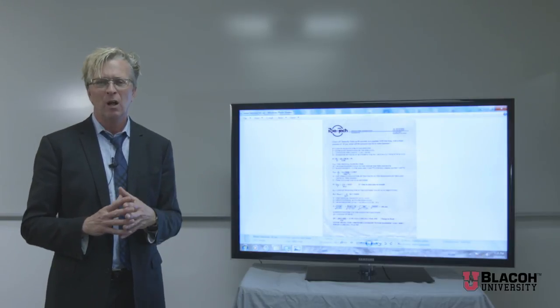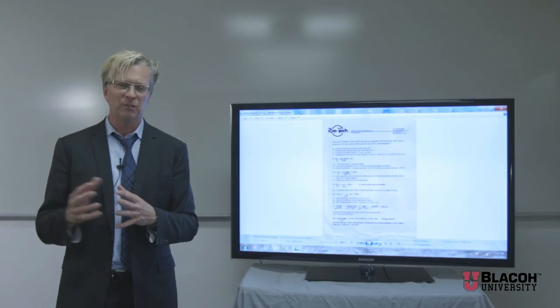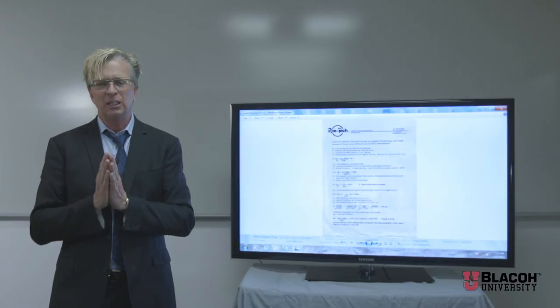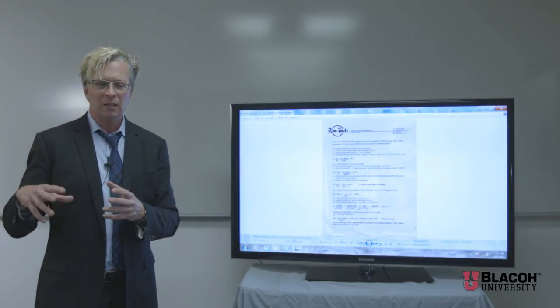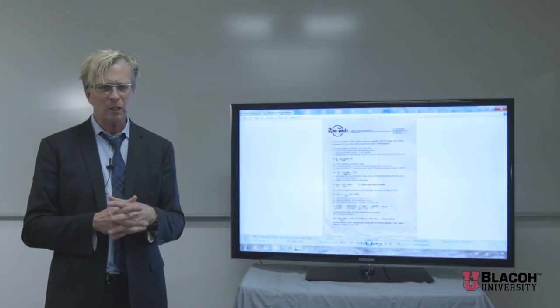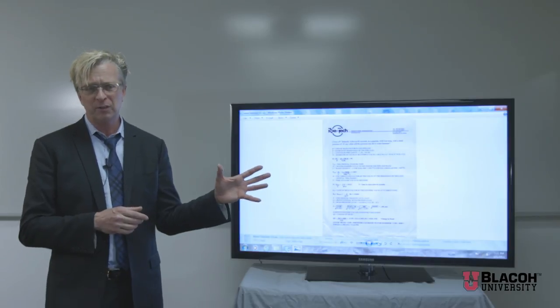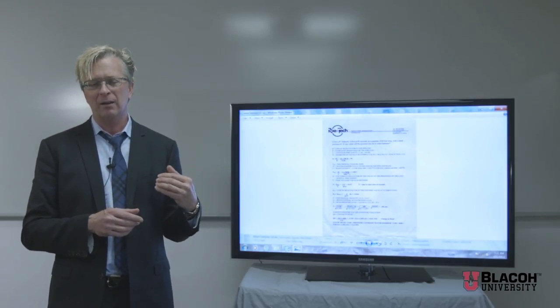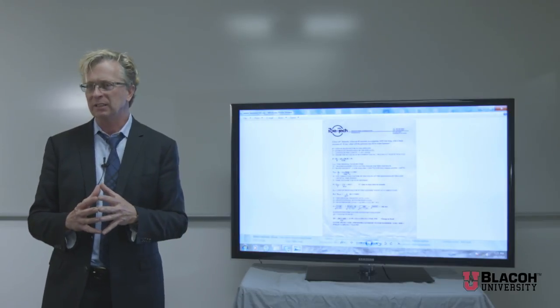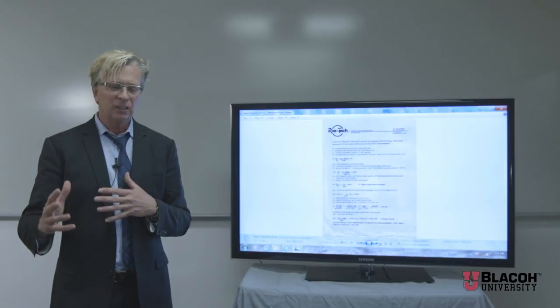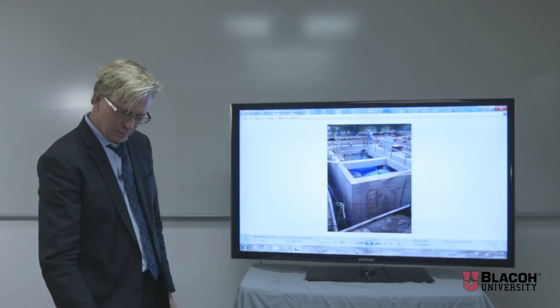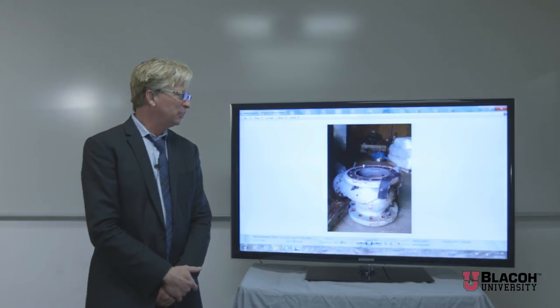This gives you basic mathematical understanding so the operator in the field can see the cause and effect. We have applications with rail cars or barges with butterfly valves they can close quickly. You might think 20 seconds is a long time. We see people closing valves in just a couple seconds. I'll show you computer analysis where we have emergency breakaway valves for ships that close in two seconds, or jet fuel applications closing in one second. In these cases we have surge vessels to accept energy.